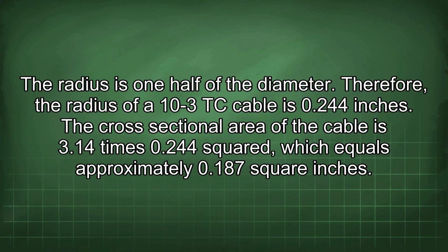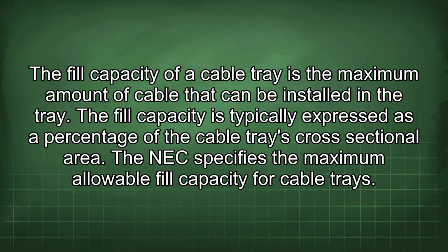The radius is 1/2 of the diameter. Therefore, the radius of a 10-3TC cable is 0.244 inches. The cross-sectional area of the cable is 3.14 times 0.244 squared, which equals approximately 0.187 square inches.